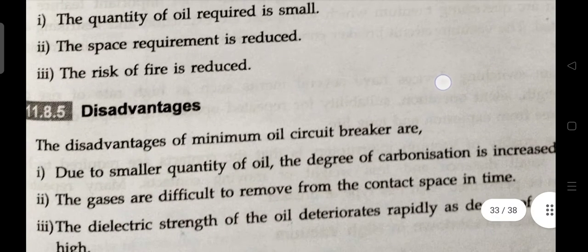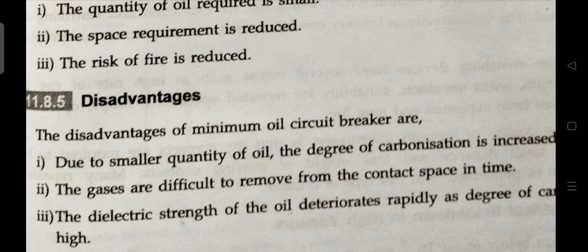The disadvantages are due to the smaller quantity of oil, the degree of carbonization is increased. The gases are difficult to remove from the contact space in time. The dielectric strength of the oil deteriorates rapidly as degree of carbonization is high.